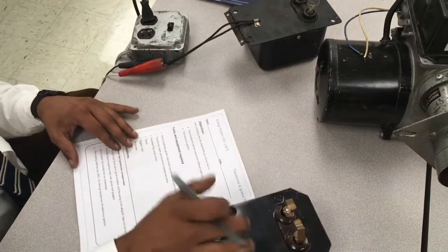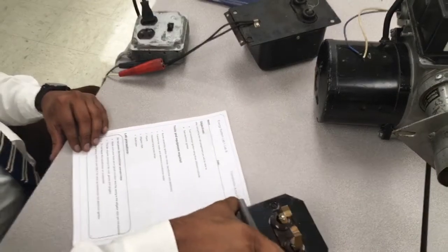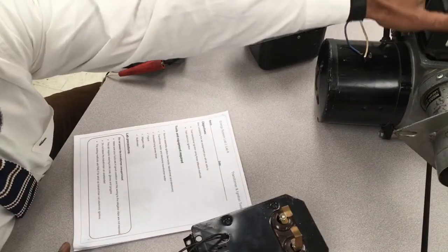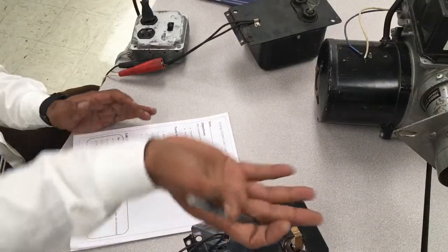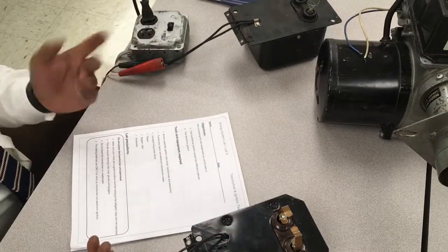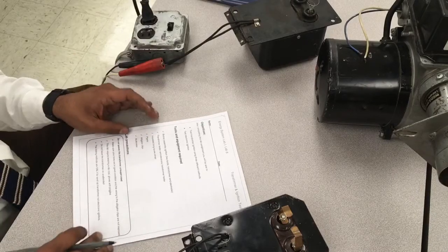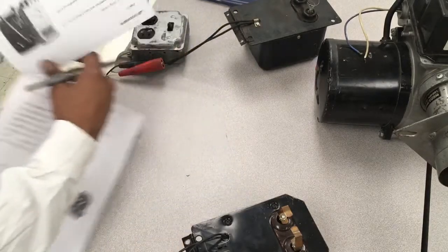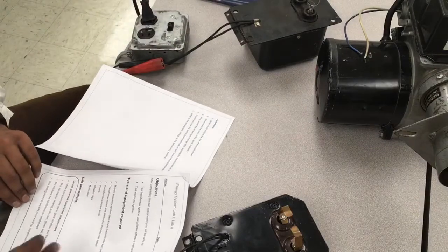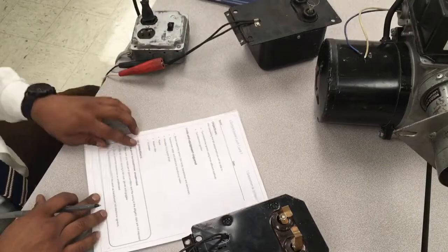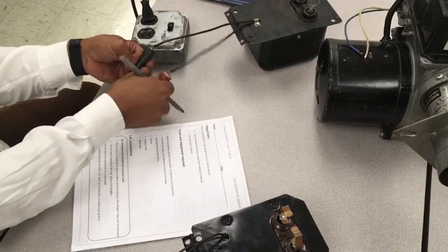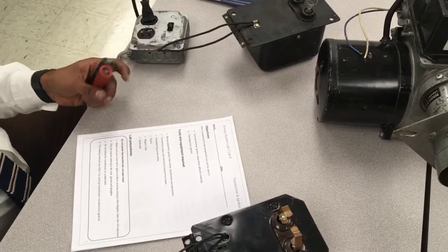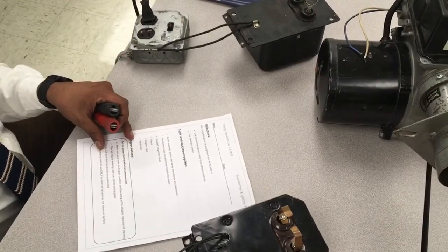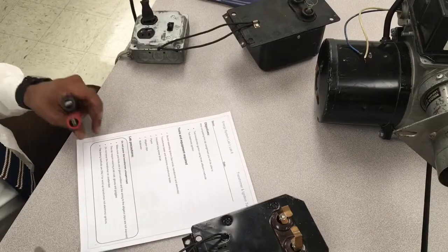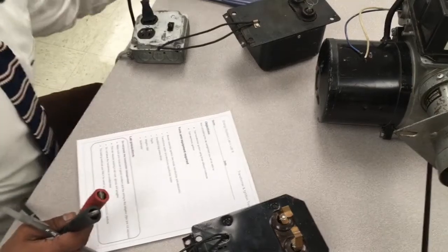So this is the transformer. It will be mounted on top of the boiler, of the burner, just like so. You can take it out, but it's very heavy. Sometimes if you tilt it backward, it might break the hinge. So before you perform the lab, make sure you have your alligator clips, a multimeter, pliers or a screwdriver to take the transformer out, and the transformer tester.